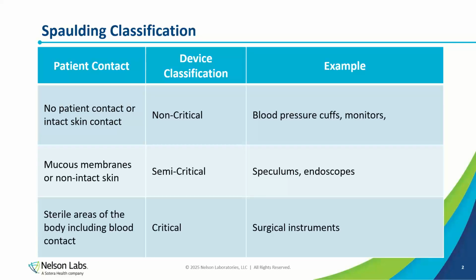that's often a really large piece of equipment, but it's not patient contacting. And as mentioned in the question, oftentimes it's going to be covered, or at least is intended to be covered, with some sort of sterile covering or sterile drape. And so with those parts of the device, I would classify that portion of the robotic equipment as non-critical. So going back to the Spaulding classification that I discussed earlier, you're going to need to ensure that that part of the robotic equipment can be adequately cleaned. And in this case, I would probably recommend an intermediate level disinfection, just in the off chance that that sterile drape is compromised and maybe the robotic arm comes in contact with blood or other bodily fluids during the procedure.